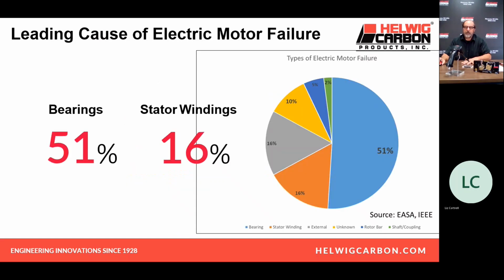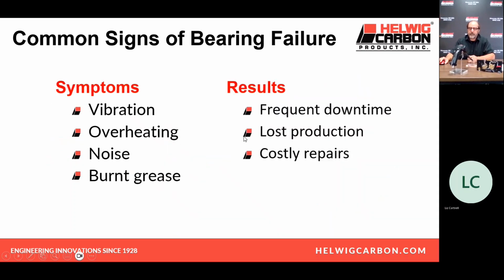Let's get started. Leading causes of electric motor failures. You can see 51% of the failures are from bearings in your electric motors. Half the failures of the motors are due to electrical wear of one form or another. This is a bad thing. This is what we're here to talk about and address today. And this is not our stat. This comes from IEEE.